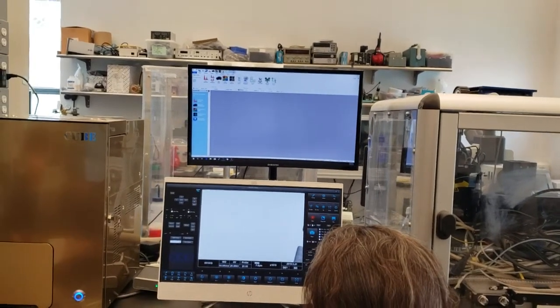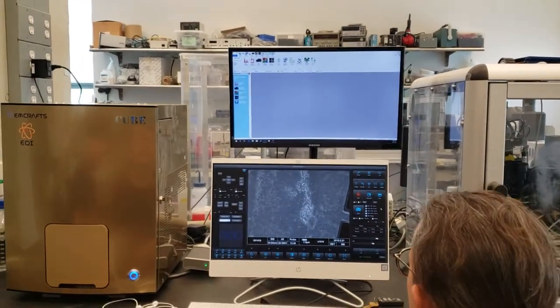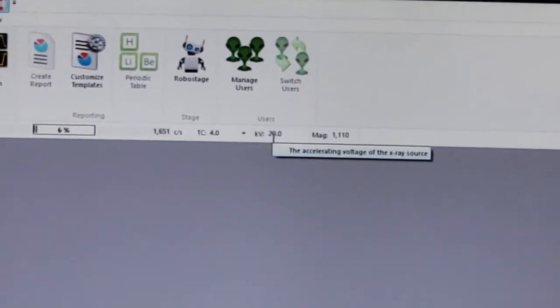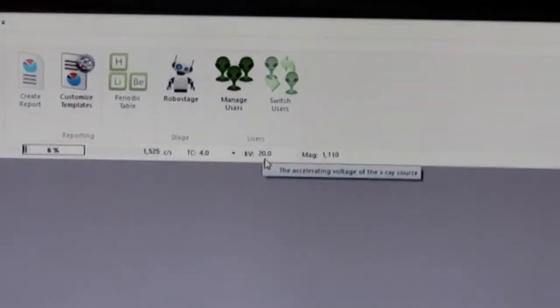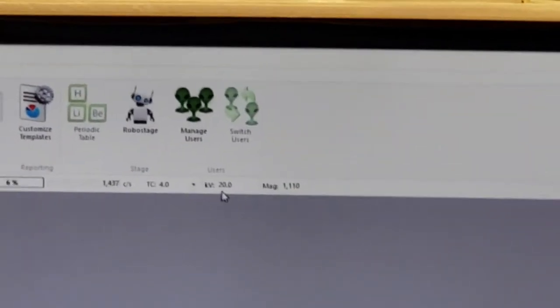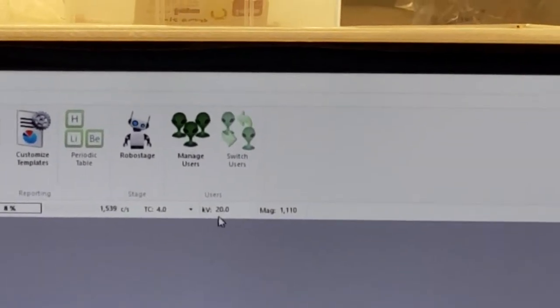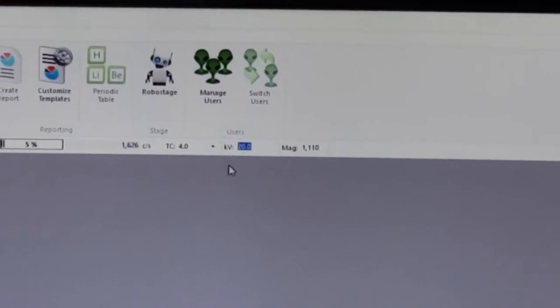The next thing I'm going to talk about, I'm going to change the spot size again. I'm going to bring this down to about 13 again. The next thing I'm going to talk about is KV. See acceleration voltage up on here? See this KV 20? We're not reading the KV off the microscope. We will be reading it off the microscope when we do our next software update. So that's going to happen, but for now, temporarily, Alex, you're going to be inconvenienced. Manual. You're going to have to put this manual number in.